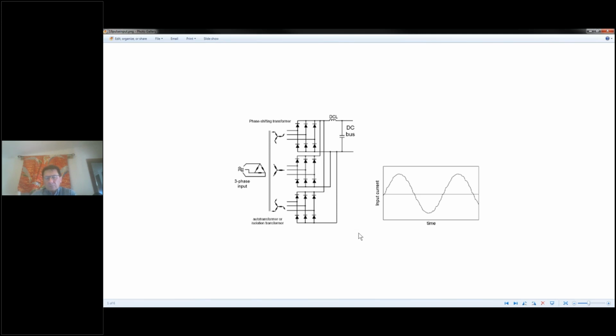So, one more point before we move off of the 18 pulse discussion, and that is that there's another type of transformer that was used out there. The transformers here are isolated transformers between the primary and the secondary, and you have separate windings for the primary and, in this case, the three secondaries.